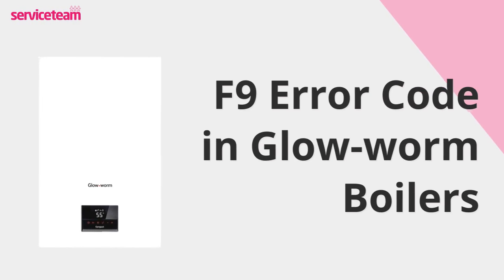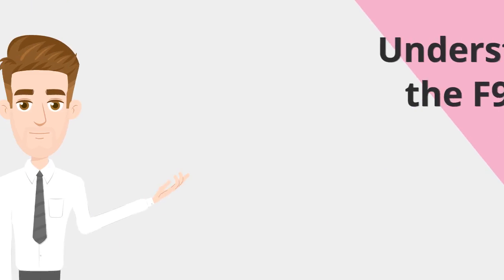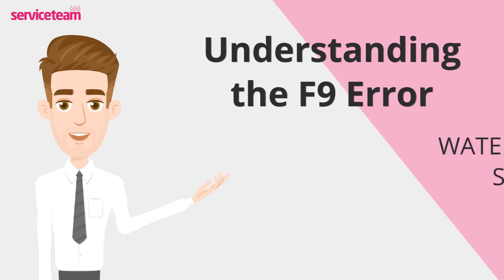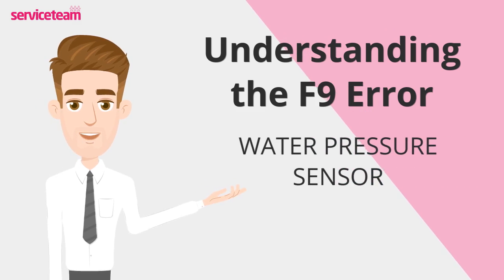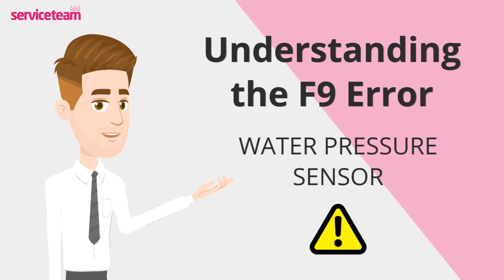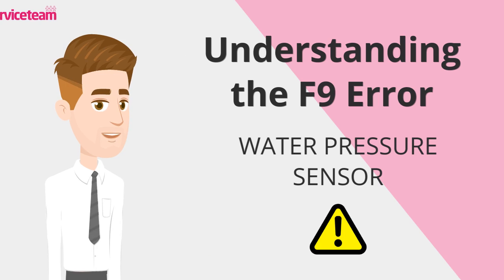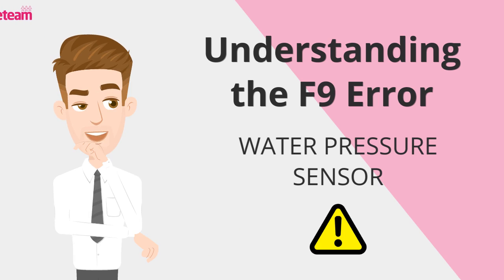Let's figure out how to resolve the F9 error code on the Glow-worm boiler. The F9 fault code on a Glow-worm boiler means there's an issue with the water pressure sensor. This sensor is important for keeping the right water pressure in the boiler system. If the sensor isn't working correctly or shows wrong readings, the boiler displays the F9 error code to avoid any further problems.